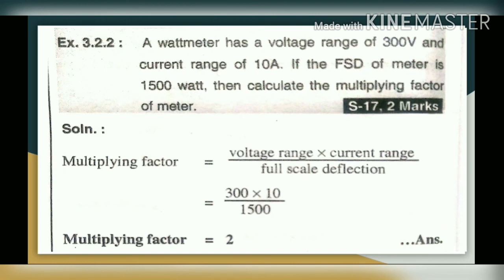Numerical 2: A wattmeter has a voltage range of 300 V and a current range of 10 A. If the full scale deflection (FSD) of the meter is 1500 W, calculate the multiplying factor. Multiplying factor = (Voltage range × Current range) / Full scale deflection = (300 × 10) / 1500 = 3000 / 1500 = 2. Answer: multiplying factor is 2.